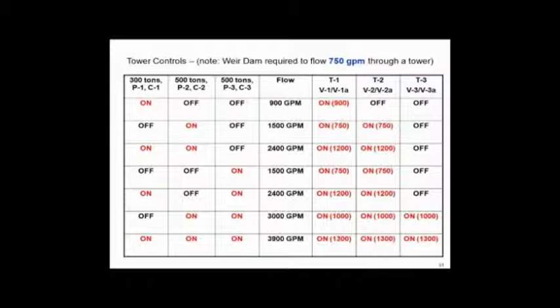Let's go through another one. Number three. I've got the little chiller and one of the big chillers on line. I got C1, C2 on line. I got C3 off. I got a dedicated pump per chiller. So I cut the pump off. I don't have any flow. My total flow is 2400 GPM. I got 2400 GPM going out to three towers. How many towers are you going to run?